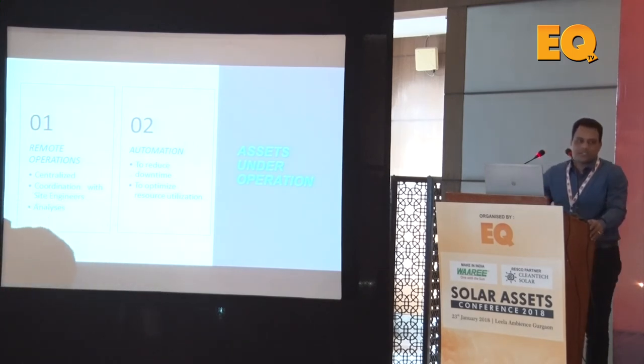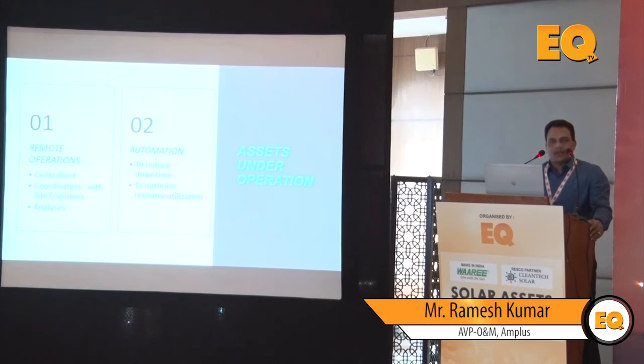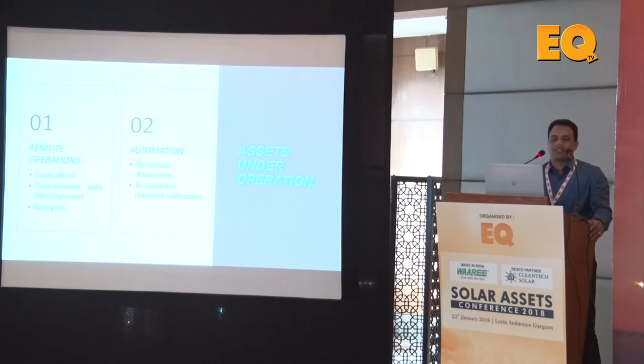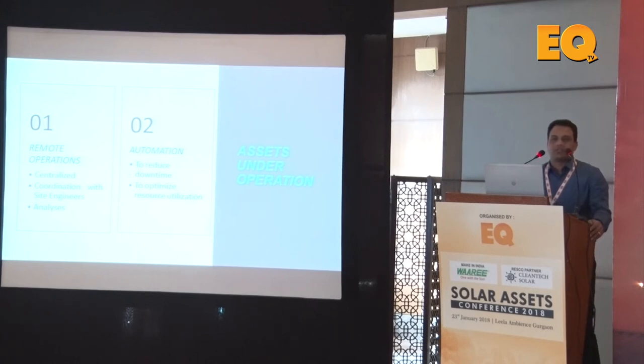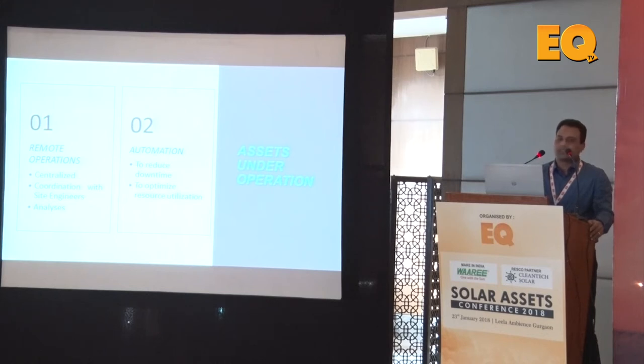The second part is automation. At Amplus, to reduce plant downtime, we have implemented an SMS alert-based system for site engineers. An SMS is generated in case of any plant breakdown if the plant is not restored within 15 to 20 minutes, so the engineer knows which site to visit. To optimize resources across 20 to 25 sites spread over 150 to 250 kilometers, we have given tablets to field engineers with built-in checklists for preventive and breakdown maintenance, with photographs uploaded instantly to the ERP system.